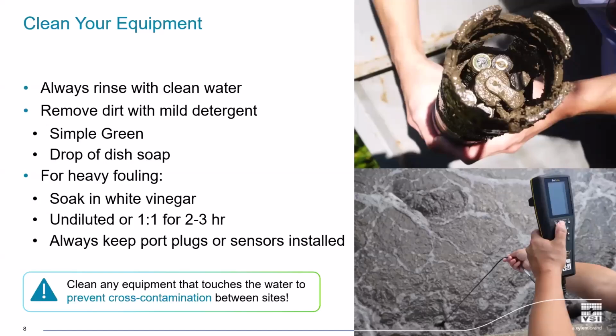But if you need to remove stuck-on dirt or growth from your equipment, you can use a brush and mild detergent like Simple Green spray or a few drops of dish soap to help you get it off. And then if you have hard growth or something like barnacles, stubborn buildup, a white vinegar soak can really help dissolve and loosen it. You can use undiluted vinegar or 1-to-1 vinegar to water. And then if you have instruments with removable sensors, in general, it's a good idea to keep either port plugs or sensors installed in your instrument when you do any kind of vinegar soak.